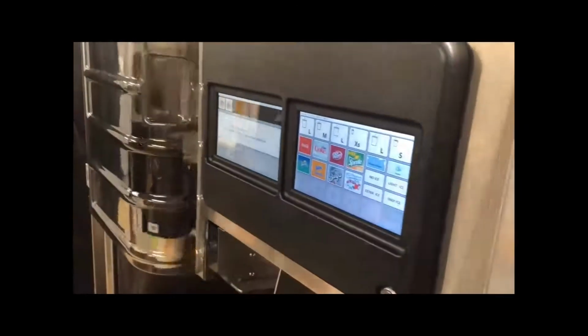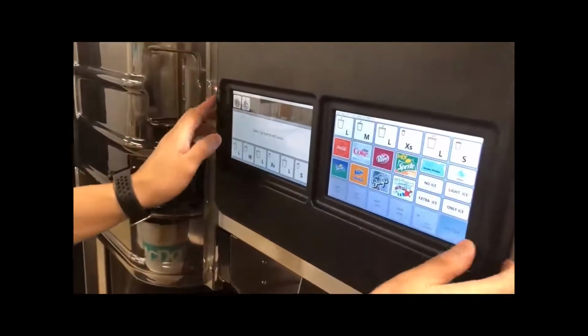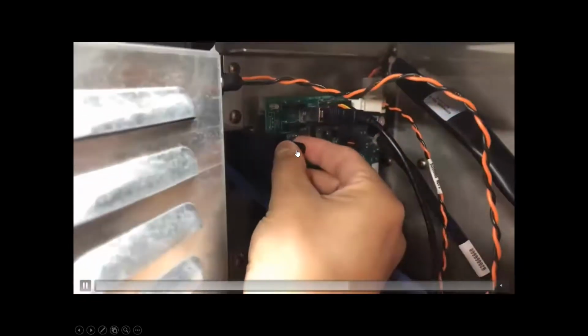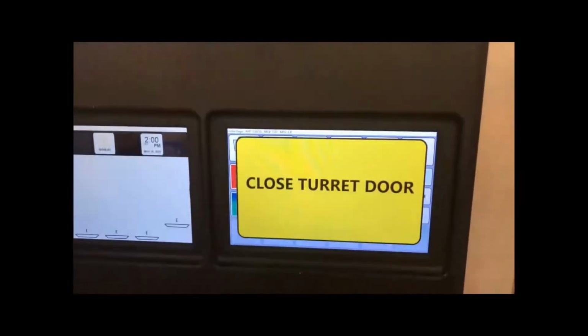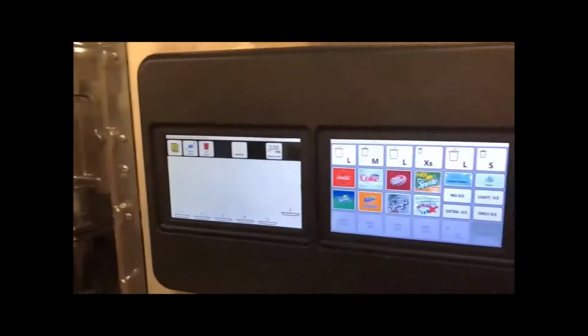If for some reason the turret door solenoid is not working electronically, behind the UI display you find the turret door solenoid. You can pull on this knob to override the electronic circuit so you can open up the turret door if that solenoid goes bad. Those are the two proper procedures for opening the turret door on the ABS 2.0.